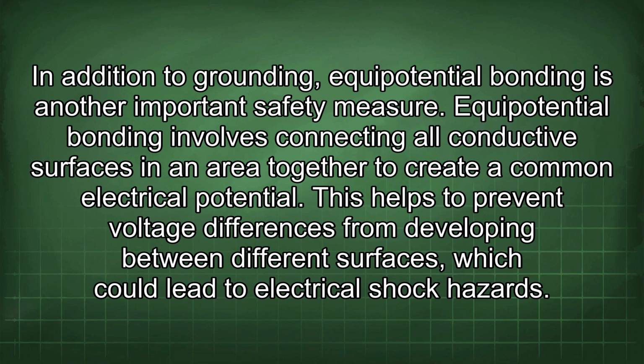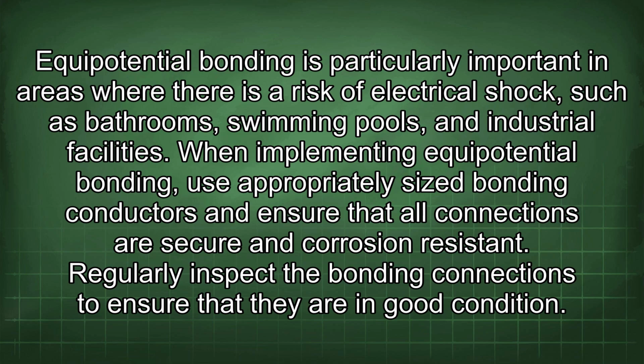In addition to grounding, equipotential bonding is another important safety measure. Equipotential bonding involves connecting all conductive surfaces in an area together to create a common electrical potential. This helps to prevent voltage differences from developing between different surfaces, which could lead to electrical shock hazards. Equipotential bonding is particularly important in areas where there is a risk of electrical shock, such as bathrooms, swimming pools, and industrial facilities. When implementing equipotential bonding, use appropriately sized bonding conductors and ensure that all connections are secure and corrosion resistant. Regularly inspect the bonding connections to ensure that they are in good condition.